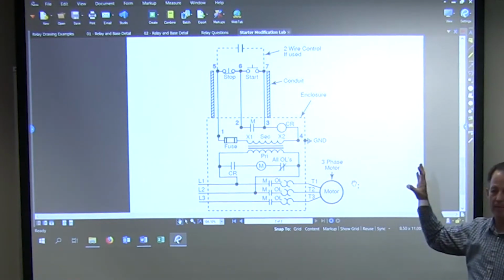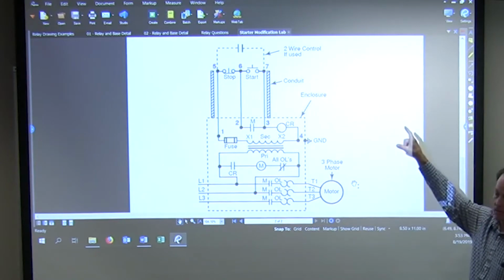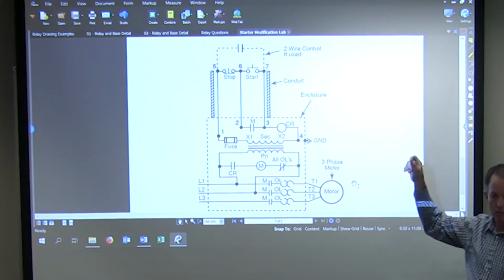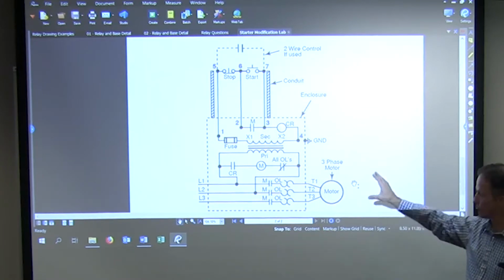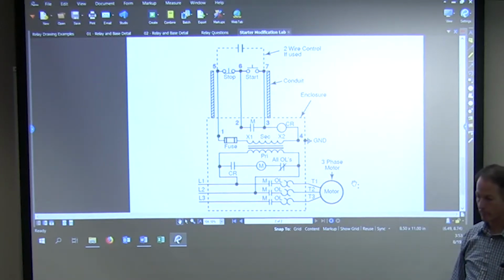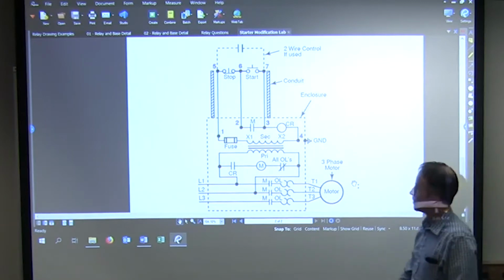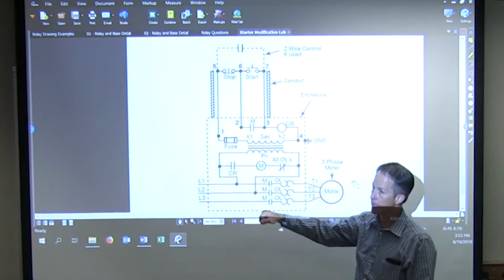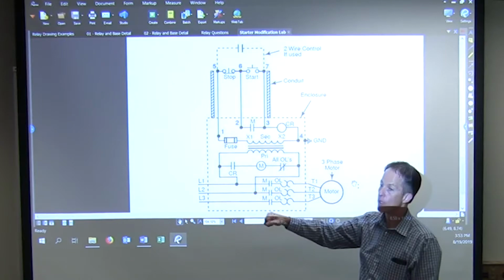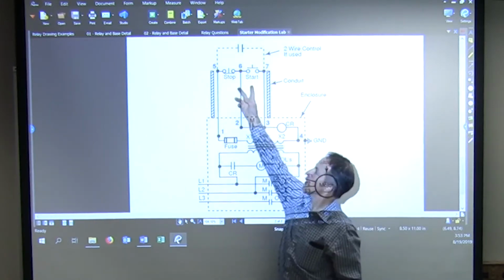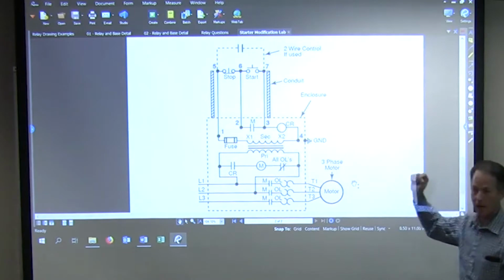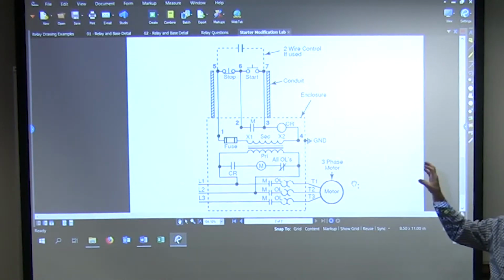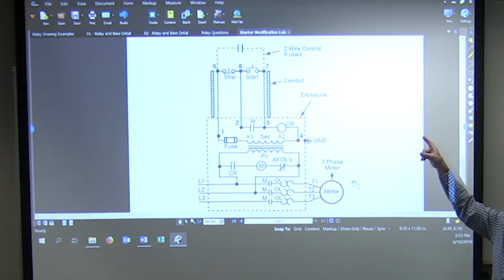What would I have to change to get that top piece so that it would start and stop this motor? Remove the wire between 5, 6, 7. Remove the two momentary contacts. The momentary contacts, or you remove your stop and start switches? The buttons. Remove the stop and start buttons to make this work. So then would it be a momentary control from the control system, or a sustained held output? Either 24 volts or 0 to 10 volt control.